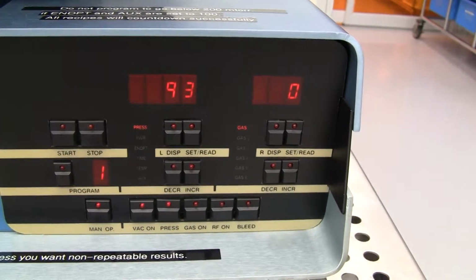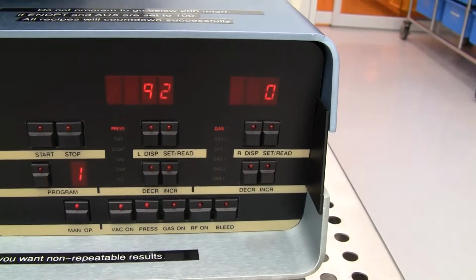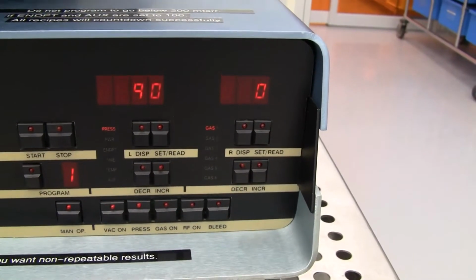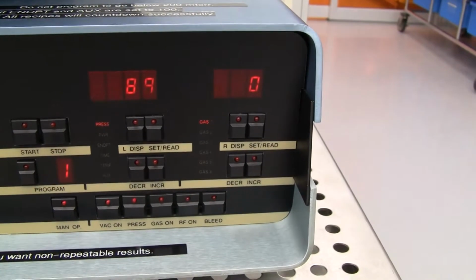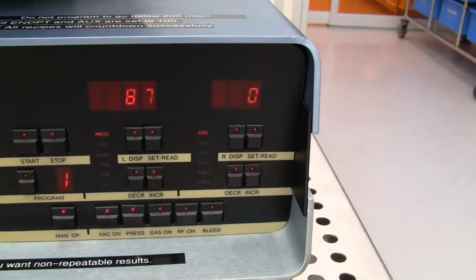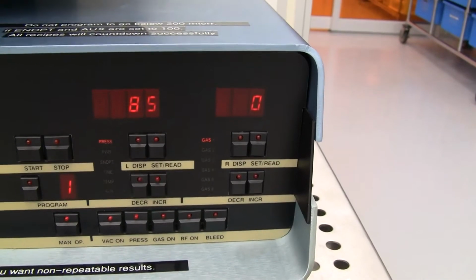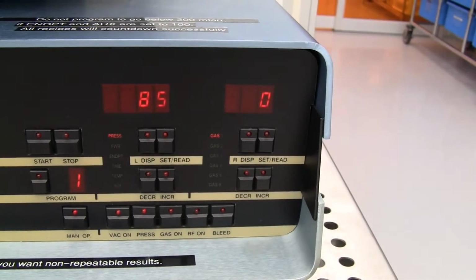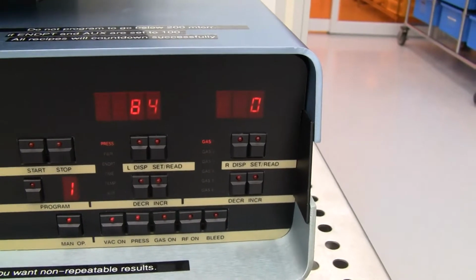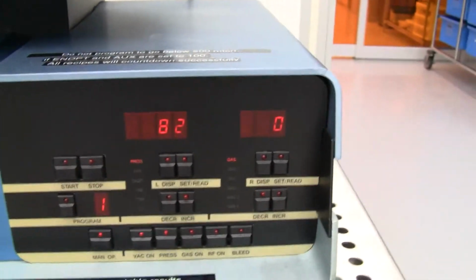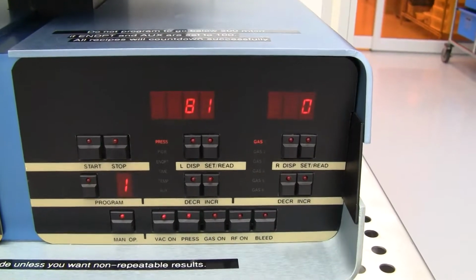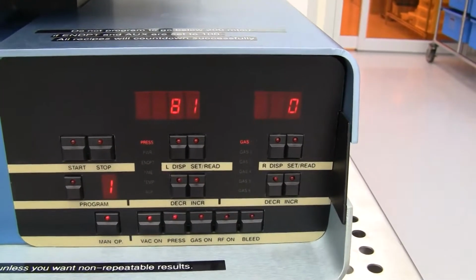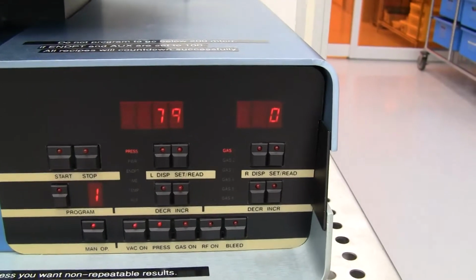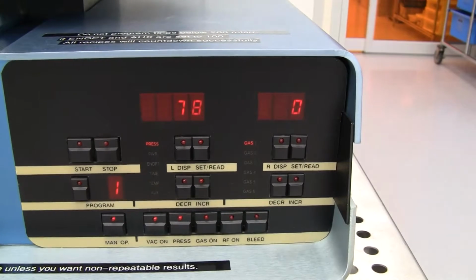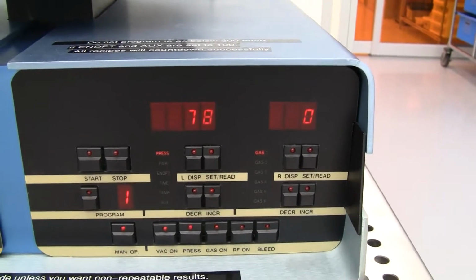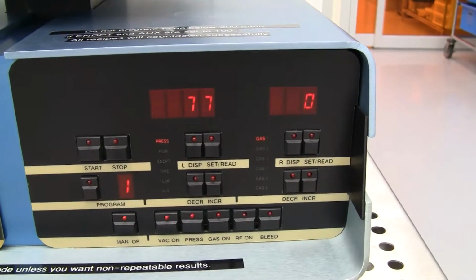I'll let it go to, I guess, about 70, and see how quickly it leaks back up. It's going down to 50 pretty easily, which is a little bit confusing. If I'm getting nitrogen in there, then it seems like I'd have a leak, and that's a pretty good base pressure for a chamber that's got a leak. All right.